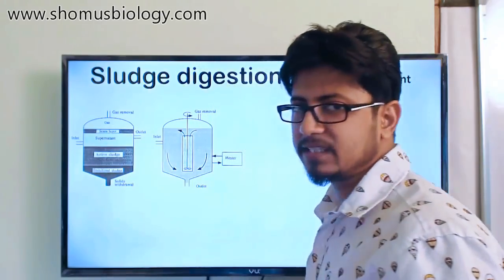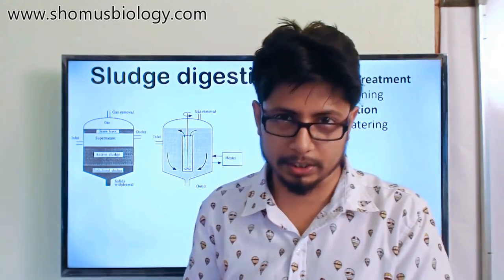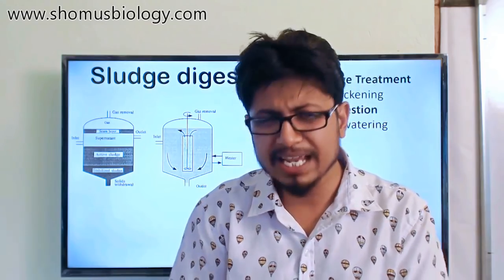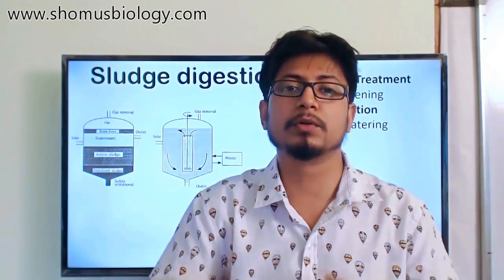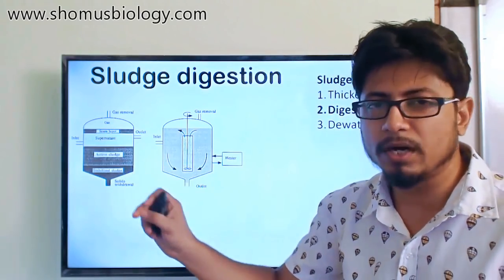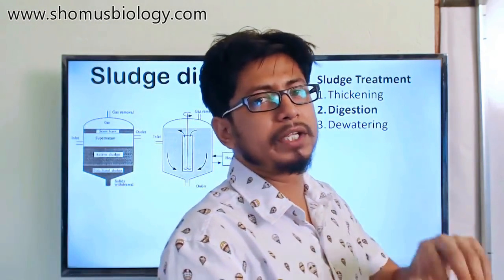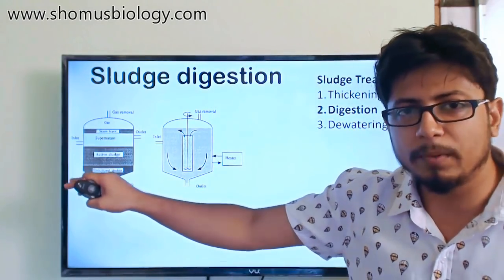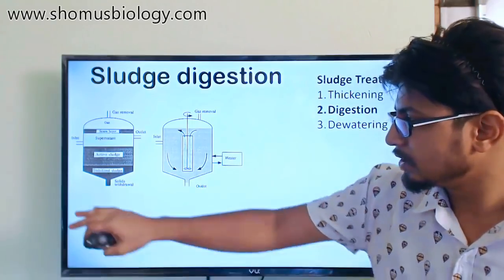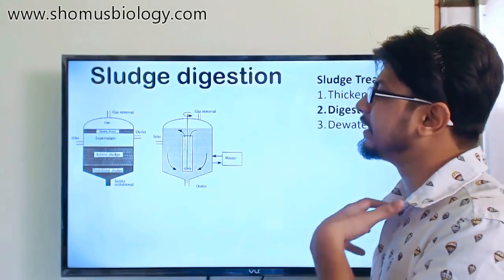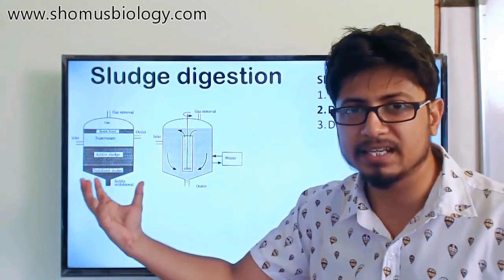Active sludge contains living microorganisms and all the sludgy qualities — it can still provide nutrients to microbes in wastewater. Stabilized sludge, on the other hand, no longer contains living microorganisms, and its chemical properties have been modified so it can no longer provide nutrients to support microbial growth in secondary treatment. The goal of the digestion chamber is to convert as much sludge as possible into stabilized sludge.